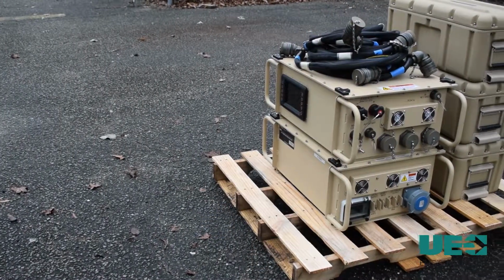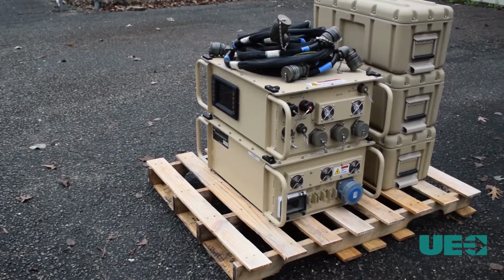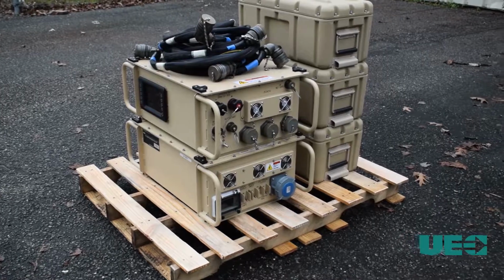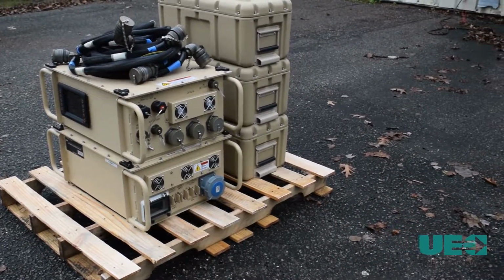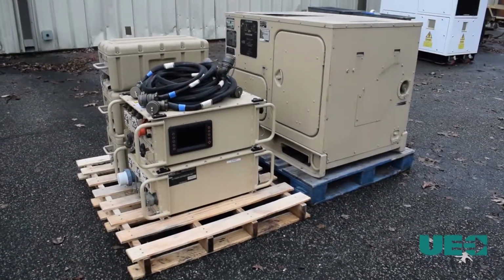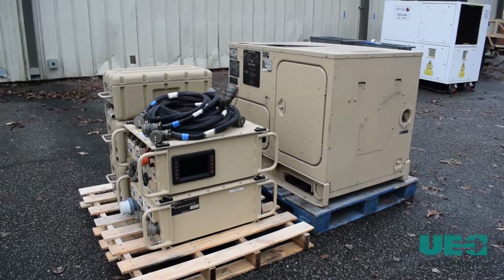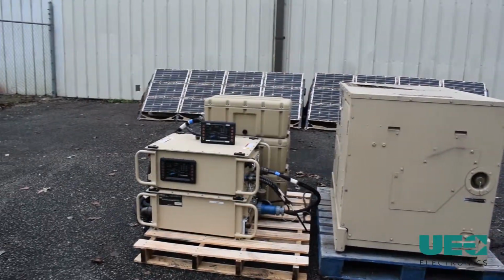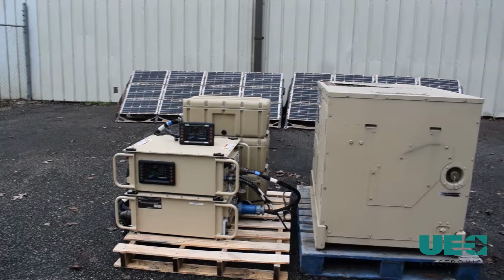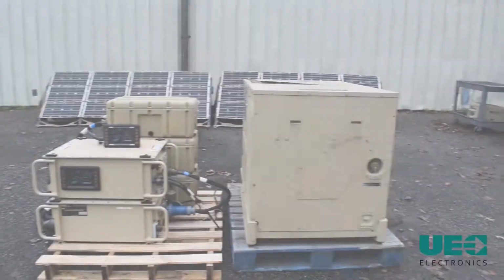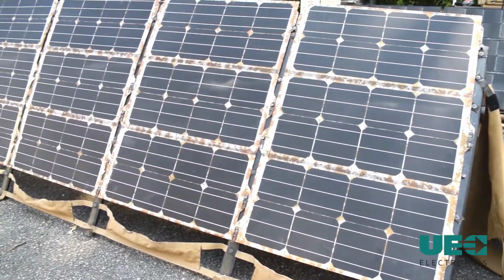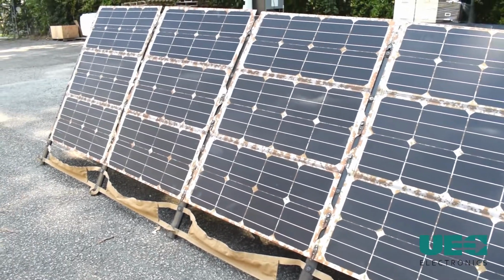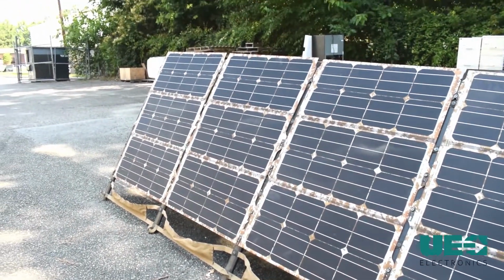Connecting the modular components. Now that you have considered where to operate the system, please take the following steps to connect all the modular components. The first step for setup is to ground the generator. After the generator is grounded, then the solar arrays can be connected to the system. Note that MEHPS does not require solar arrays, but solar collection sustainably reduces fuel consumption.